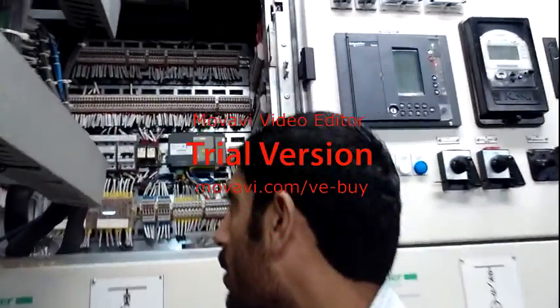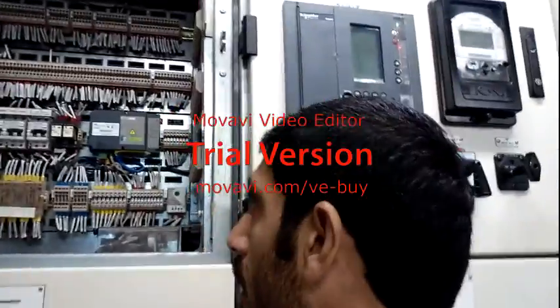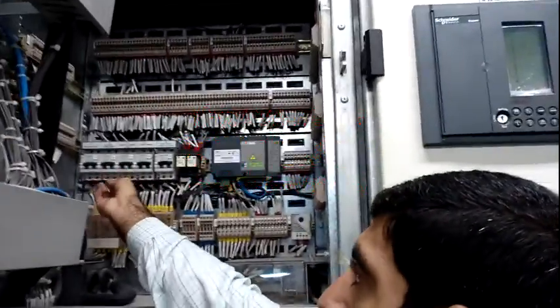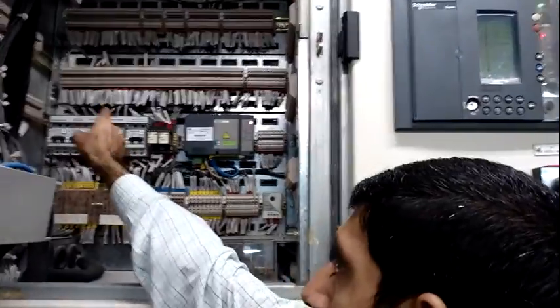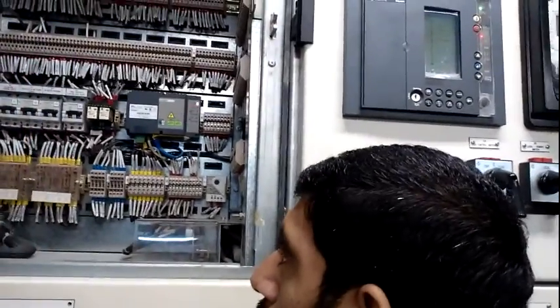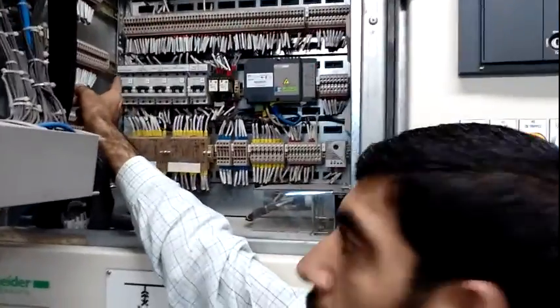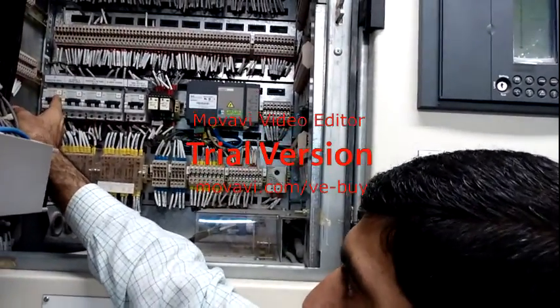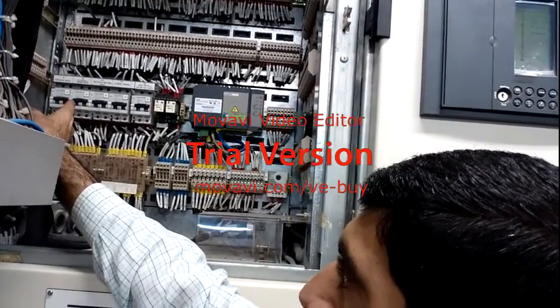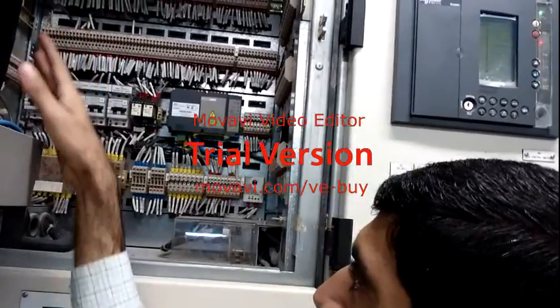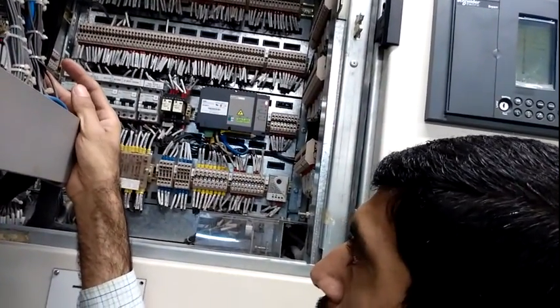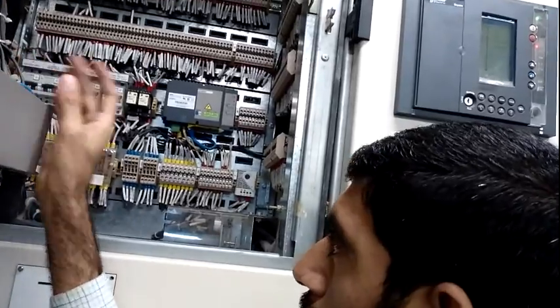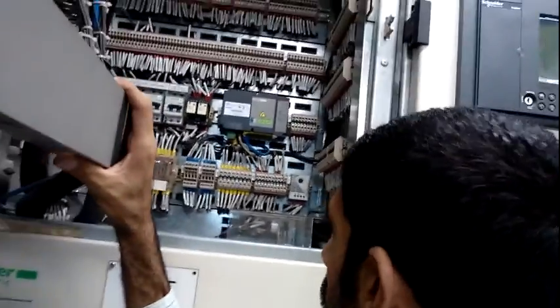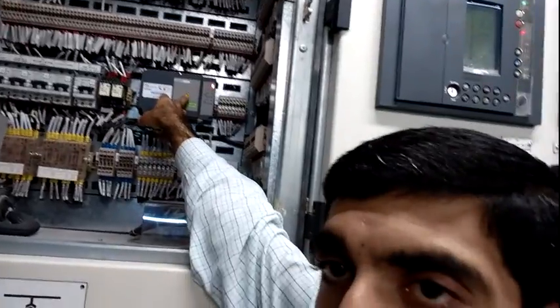Now I want to show you more about the control circuit and control wiring. First of all, I have some breakers: control breakers and auxiliary breakers. The first one is for protection, the next one is for the control tripping circuit, and then the indication and metering circuit, control, motor circuit, charging circuit, control for the breaker, and panel heating and lighting auxiliary breaker. These are small 2-pole breakers, and this indication is glowing for this module.